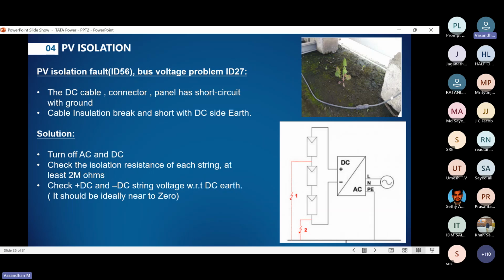Okay. And check the positive and negative string voltage with respect to DC earthing. It should ideally be near zero. It should be near zero only. Positive to negative string voltage with respect to DC earth, we need to check. Positive to earth, negative to earth, we need to check. It should be zero. So this is the isolation fault we'll get. Now, we need to do the solution.